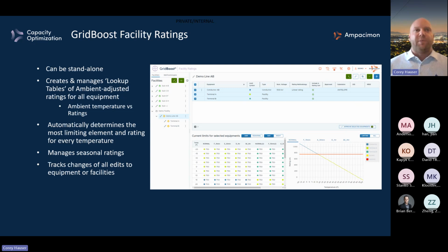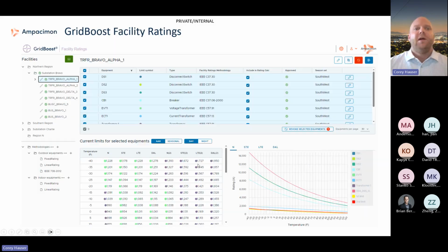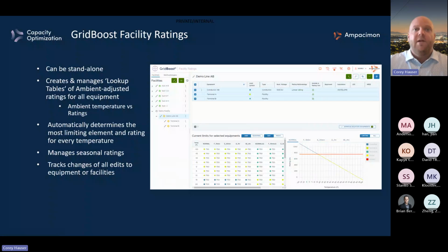What this is doing specifically is creating and managing lookup tables of ambient adjusted ratings for all the equipment, not just the facility equipment, not just the terminal equipment, not just the conductor. This is where it's really bringing it all together, looking at ambient temperature versus rating. We're automatically determining the most limiting element and rating for every temperature level. It has the different temperature spans, with the rating and the piece of equipment noted by color for each one it applies to.